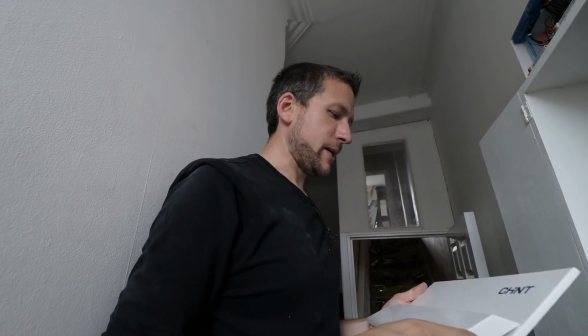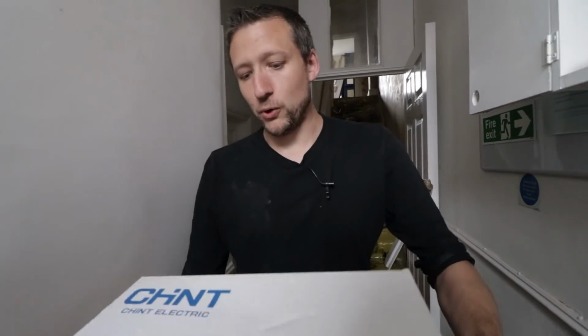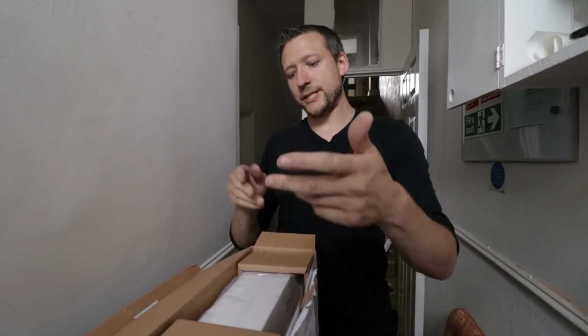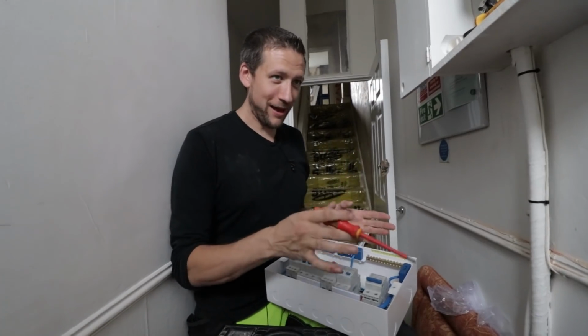But it's actually the first time we've ever fitted a brand called Chint. I've never bought it before, and it's a brand that Screwfix sell. It's okay, but it is a budget brand. I mean, there's no getting away from it. I'll give you an example. I had to buy a second brand new board to swap out the broken parts in this one. I got it, and the RCD in it was damaged, literally from the shop. So I'm just going to have to swap the RCDs over and take this one back, because you can't buy the RCD separately. Let me pull the RCD out of this one and I'll show you what's wrong with that board. A few inches later. So I'll just show you quickly before I rob this one a bit to put in that one. You shouldn't have to do that, but anyway.